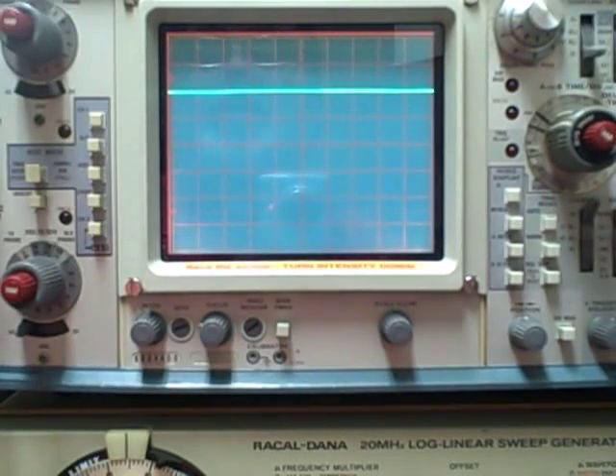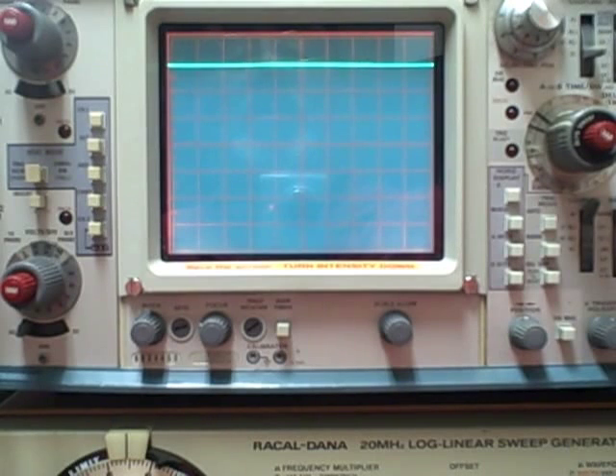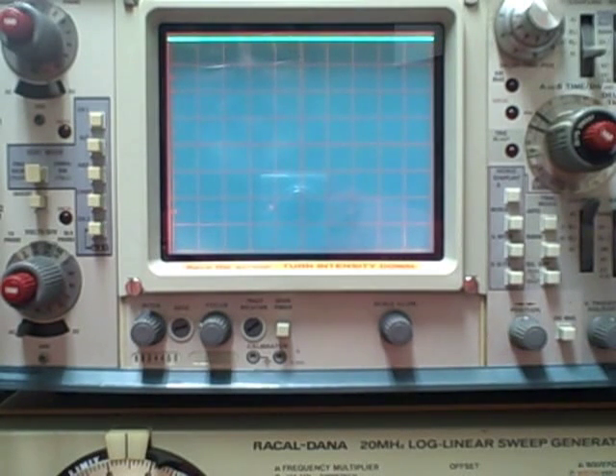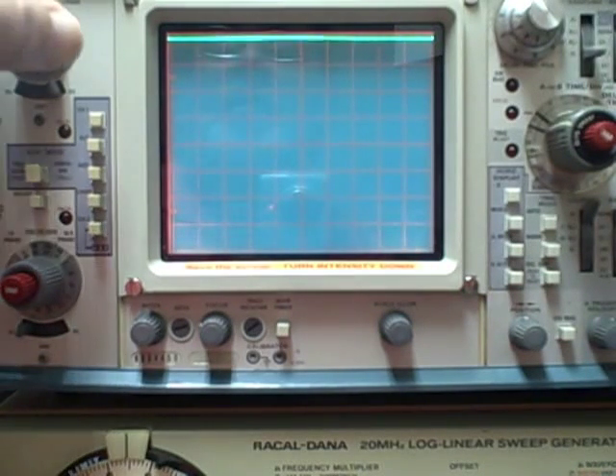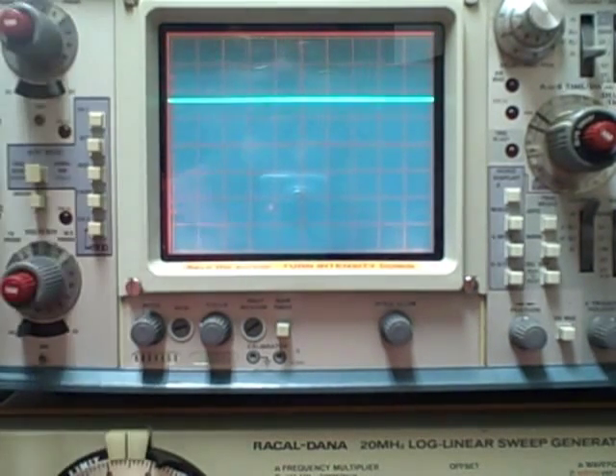So let's change the scale on our scope. We're going to go to 20 millivolts per division. We've got 40 millivolts coming in, and 20 millivolts per division means we're up 2 divisions, which is exactly where we're at. So let's go ahead and raise ourselves. There's 60. There's 80 millivolts. We're full scale again. On 20 millivolts per division, we are up 4 divisions. That's 80 millivolts. Then let's take ourselves to the next range, 50 millivolts per division.